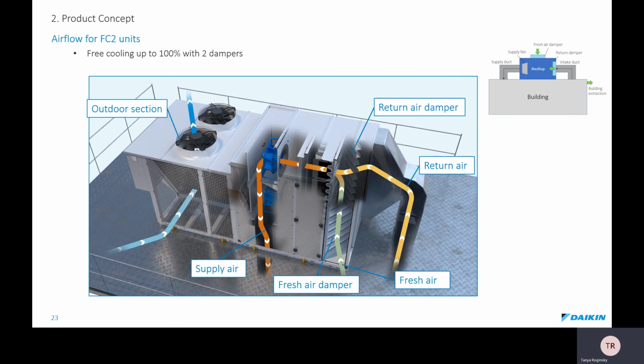Next is FC2 units. The key difference compared to the base unit is that the FC2 unit integrates fresh air supply. The FC2 version has 2 dampers, a return and a fresh air damper. As you can see, the return air goes through the return air damper and is mixed with the fresh air that comes through the fresh air damper here. The mixture of return and fresh air is filtered through the different filter sections. Then it's treated by the indoor coil to the required thermal conditions, and finally supplied to the building by means of the single or multiple supply fans, depending on the unit size.